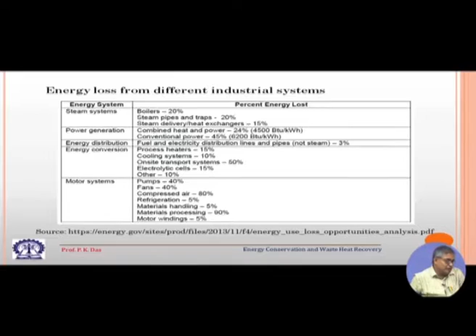Then we have motor systems like pumps, fan, compressed air, refrigeration, materials handling, material processing, motor winding. So, losses are there. You see compressed air, that is a very large figure, 80%. The reason is that when we compress a gas, its temperature increases. So, part of the work that goes for raising its pressure is converted into thermal energy, and obviously, that is a potential loss, and that gives a scope of recovery. But though the percentage has been shown, this is not the total picture. As we proceed with this lecture, we will see that not only the amount of energy is important, there are other factors which are to be considered, and then only we can have the actual potential of recovering this waste energy.